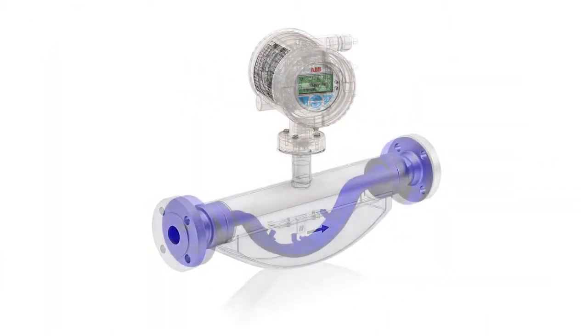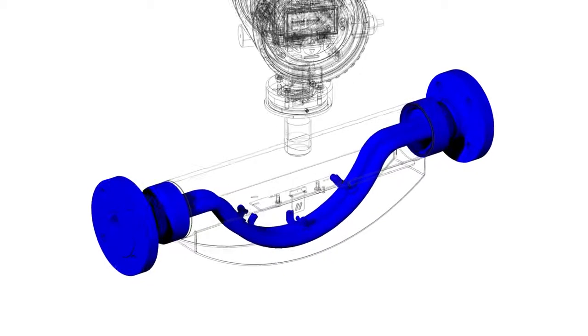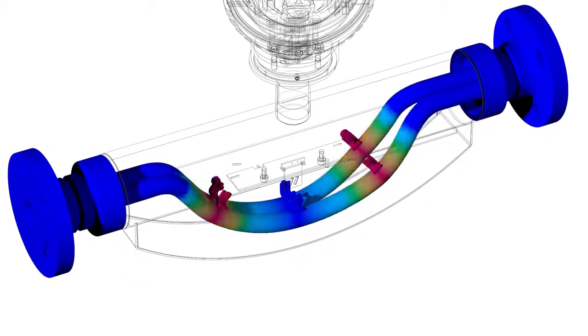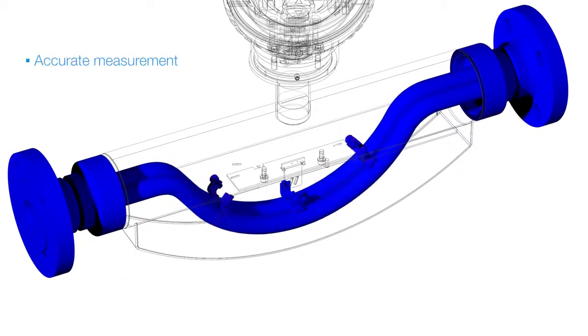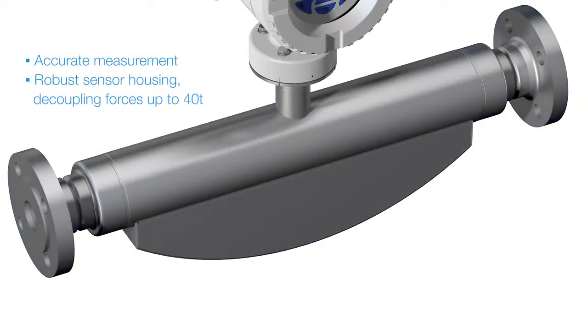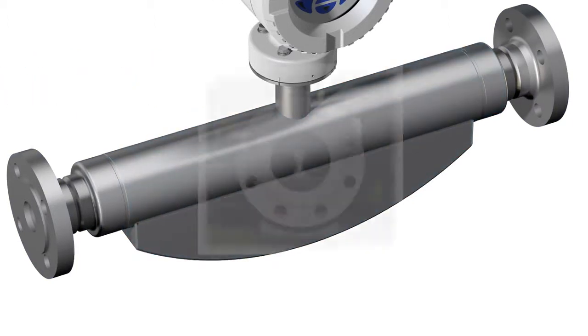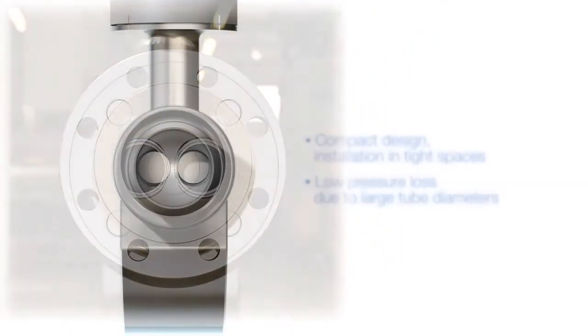The key elements of the ABB Coriolis Master are oscillating tubes. Mass flow creates a phase shift of the oscillation. A very robust sensor housing protects the vibrating tubes and eliminates interferences from outside. Larger tube design produces a lower pressure drop.